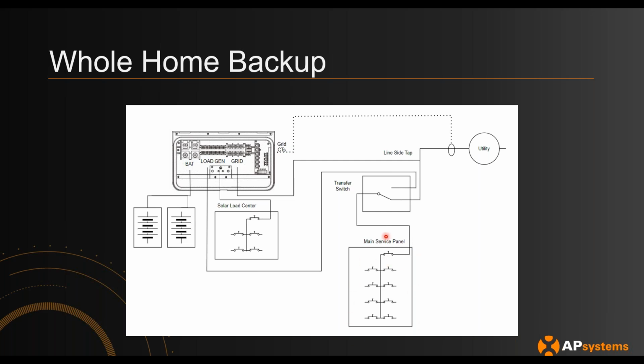The main thing I want to warn about: if it goes into backup and the main panel exceeds 11.4 kilowatts of power, the PCS will shut down to protect itself and prevent overloading. So it's important for the customer to know that in a backup scenario, they should only be using essential loads when powering the system.